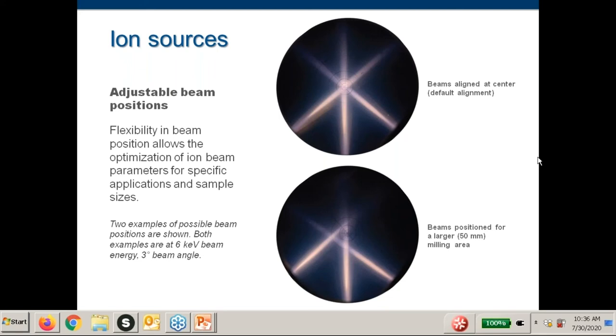Is there a special feature that could help with the backside milling of a FIB sample? That's an interesting question. I guess I have to know a little bit more about the application. Typically a FIB lamella is on the order of a few to tens of microns. Further thinning a FIB lamella, at least in our opinion, is a function more suited for a nano mill or a pico mill where you have a spot size that's smaller than the lamella itself, which allows you to remove the implantation amorphous damage without creating the redeposition. We would need to experiment with that, because you would be showering it with a relatively large beam onto a relatively small lamella.